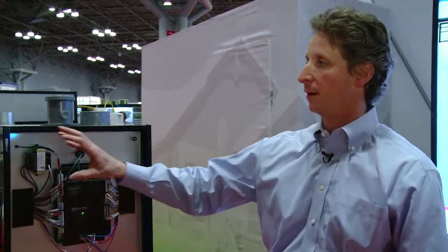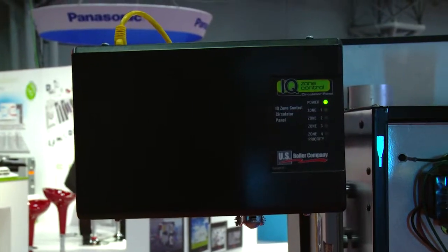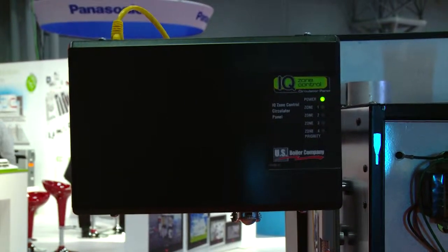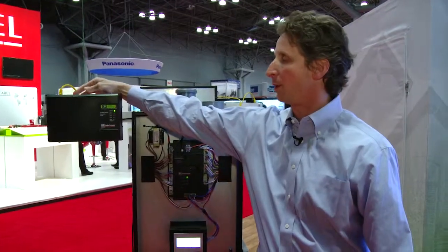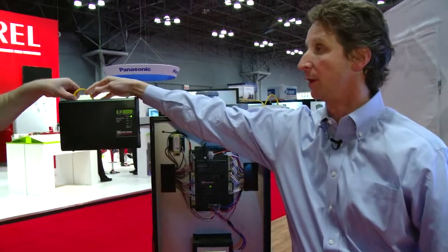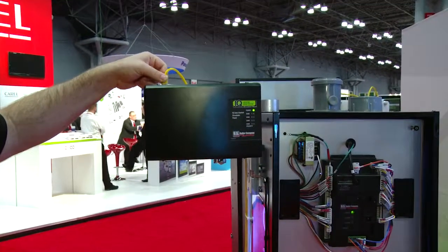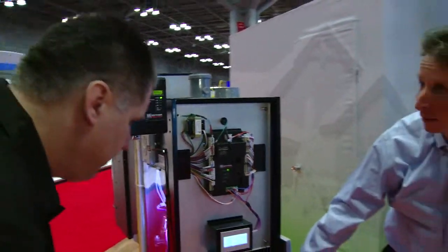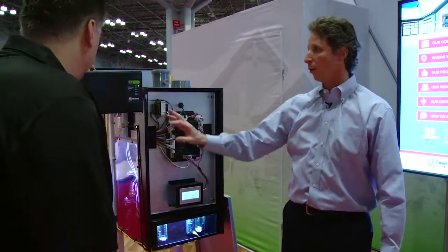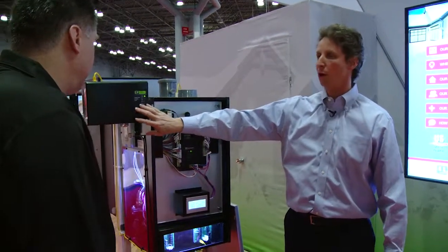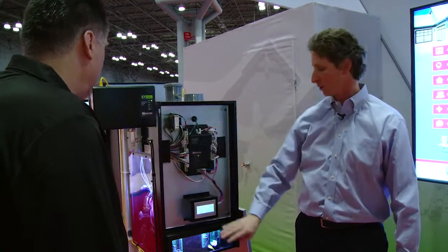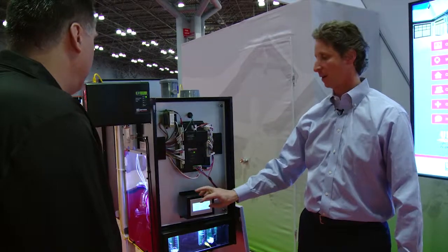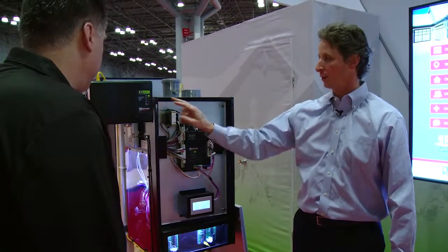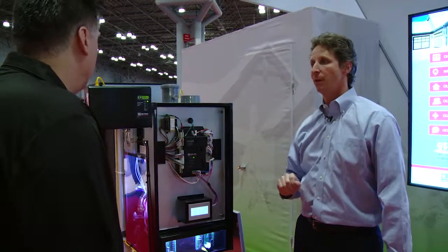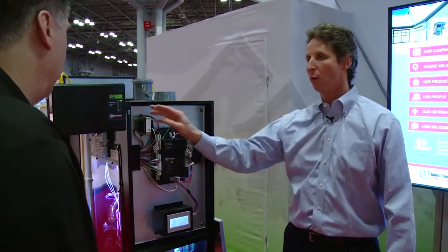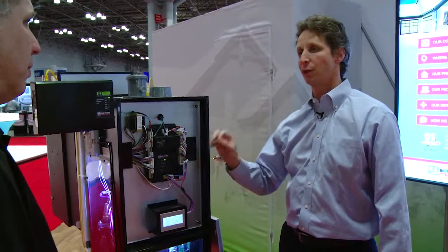Let me extend on that for a second. One of the things we've done is with this zone panel, a new zone control also coming out this year. One of the beauties of it is the only wiring between the boiler and the zone panel is this Ethernet cable, which plugs right into the board here. Once that's connected, you can run and set up your zones by size through this display. For example, you name zone 1 the kitchen, then set zone 1 to 20,000 BTUs. The boiler senses that, and when zone 1 calls, it knows all it will ever need to supply is 20,000 BTUs.